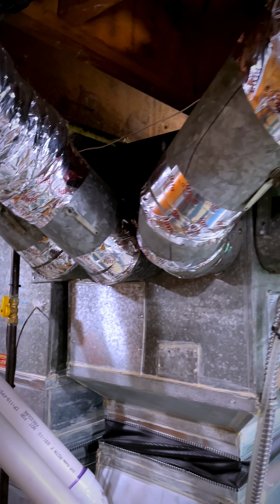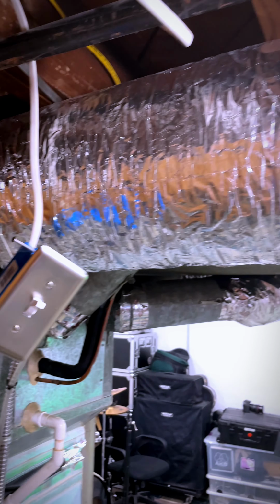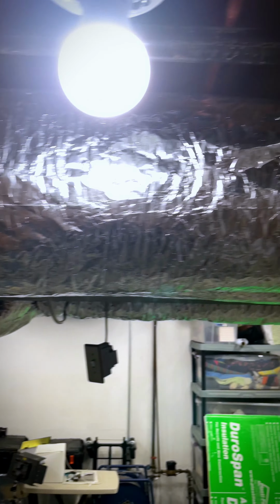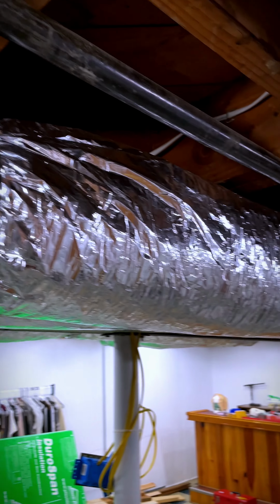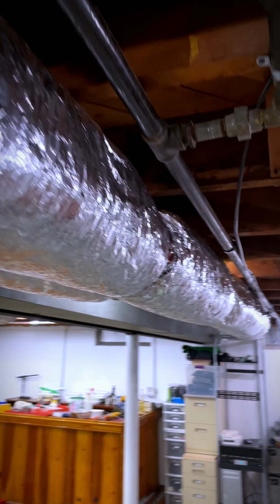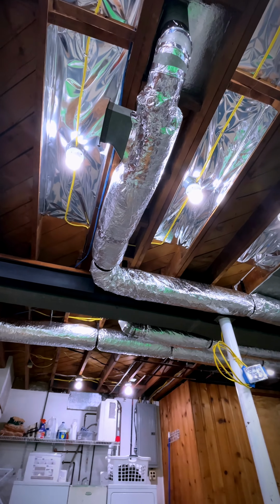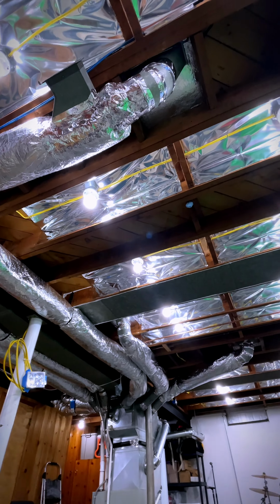Starting just after the plenum, I insulated every output run for heat and AC. This will help maintain more consistent temperatures throughout the building, as well as increase efficiency. The end of each output run is finished off with spray foam insulation in all the gaps, and then covered up with this foam core foil-backed insulation and sealed with Flex Fit duct tape.